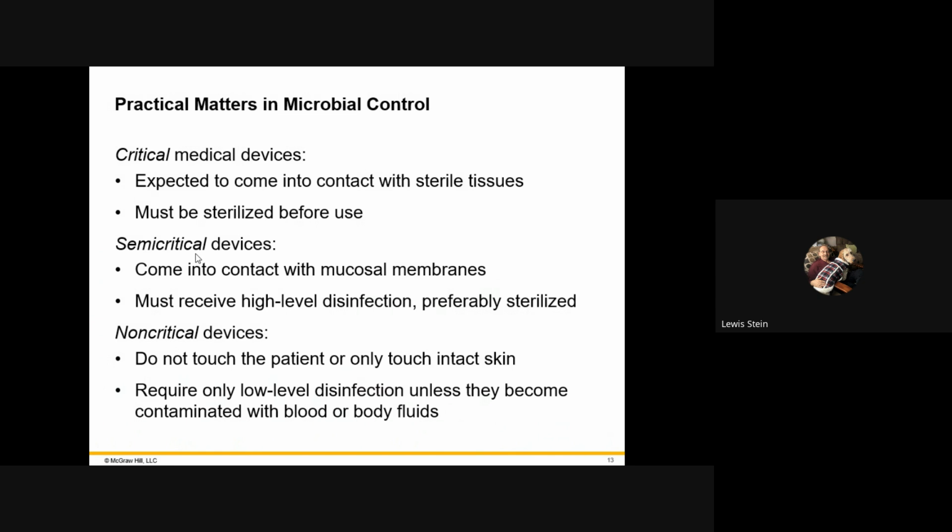They did not have to be sterilized. So what they had was a system where the manufacturer would say, okay, a typical GI lab would have 2 sets. They'd be using one. And say they endoscope somebody to look inside their stomach for an ulcer, like they did with me many, many times. And then when that one was done, they put it in this disinfecting system, and they get somebody else. They pull the sterile one, the one that was now disinfected, out, and use that.